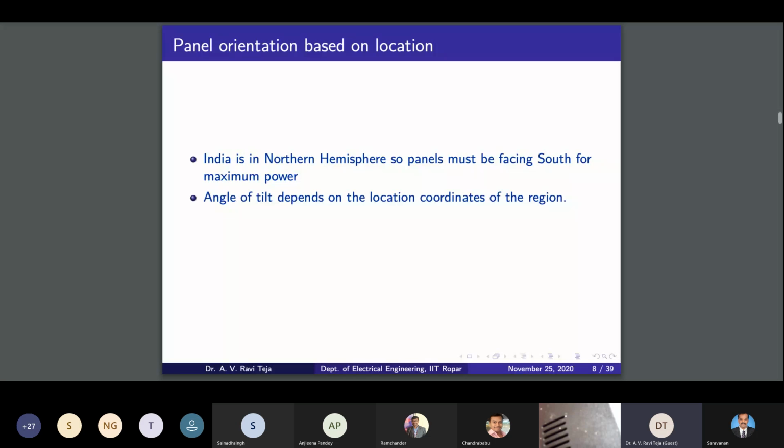So this angle of tilt, the tilt means the angle at which I place my panel, depends on the location coordinates, latitude and longitude. Based on that, you have to see for maximum part of the day, at what angle if I tilt my panel, I will get maximum power.